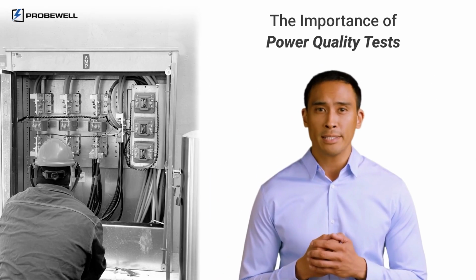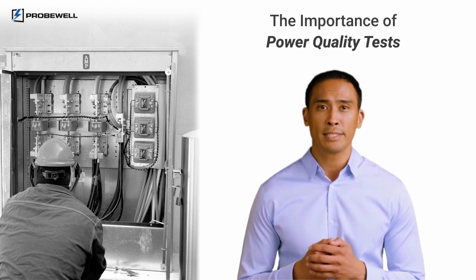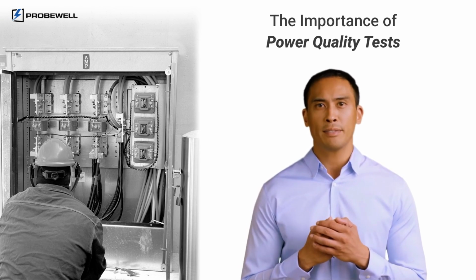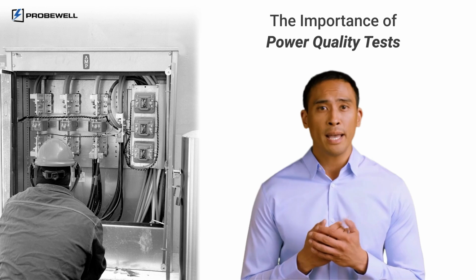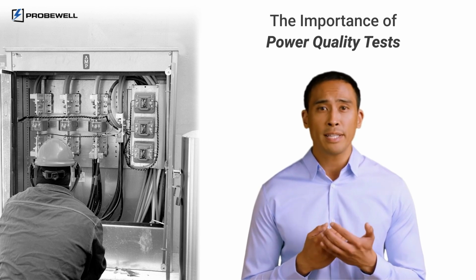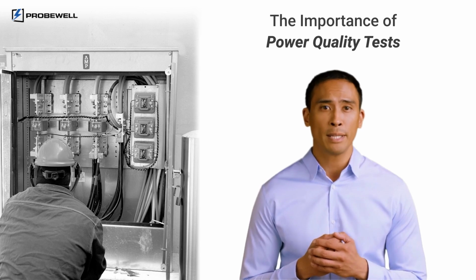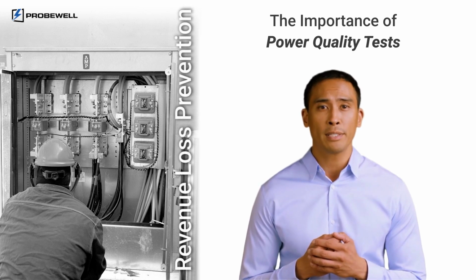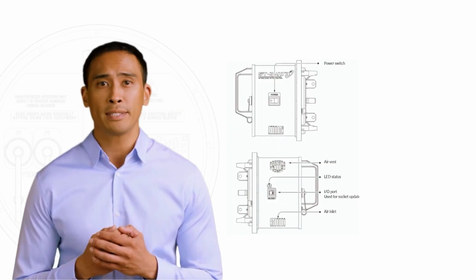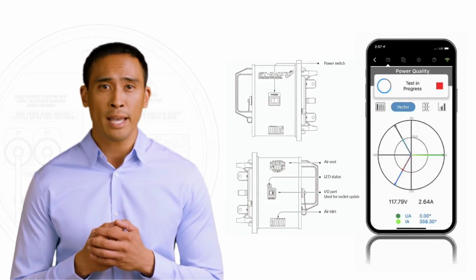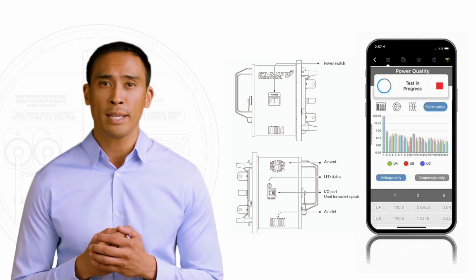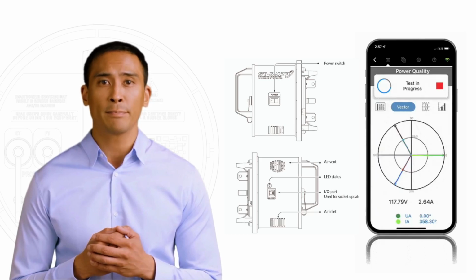Regular power quality tests are crucial for maintaining safety and efficiency in your CT-rated installations. Early detection of high harmonic distortion allows for preventive measures, protecting equipment, improving site reliability, and contributing to effective revenue loss prevention. In this mode, the XT Series tester acquires real-time measurements for secondary voltage and current on all connected phases. We'll cover everything from initial setup to test execution and interpreting results, ensuring the highest standards of power quality in your installations. Let's get started.